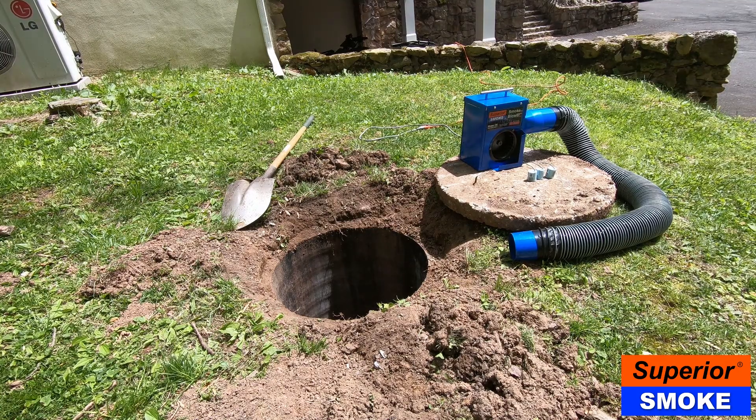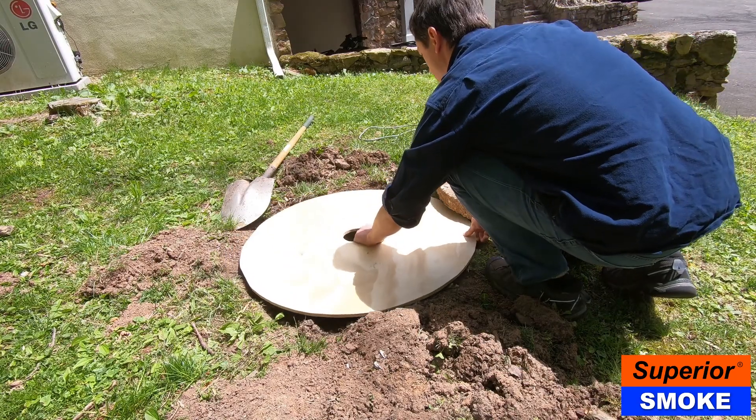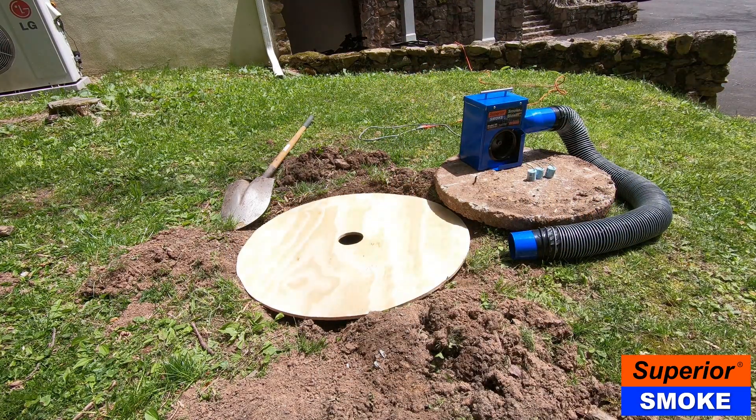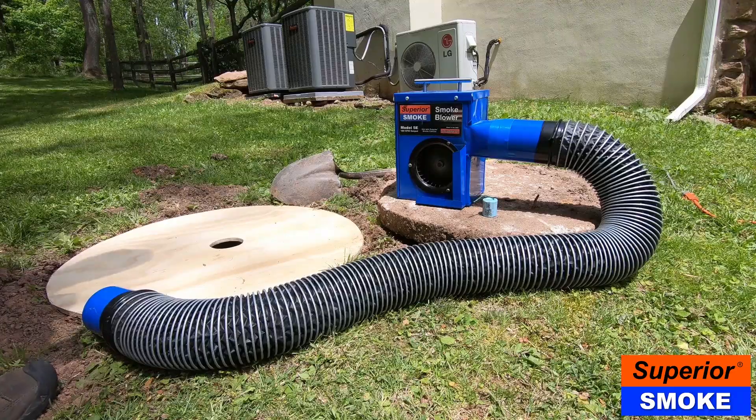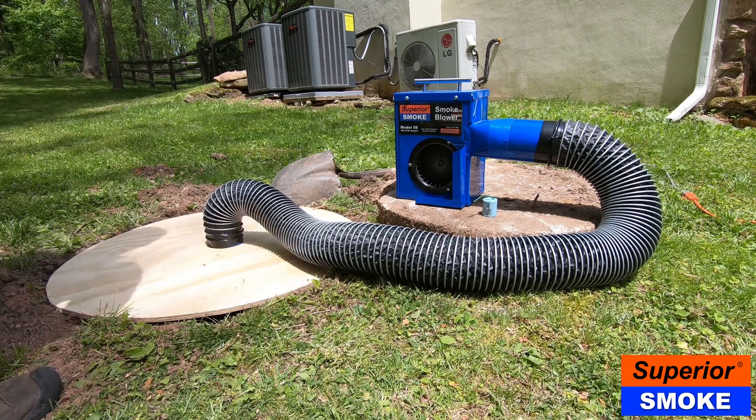The process is simple. First, find a clean-out or other access point to the plumbing system. If you already have the lid removed from the septic tank, this is a perfect place to introduce the smoke. Place your plywood board over the lid. Next, take the end of the flexible hose and place it in the plywood board.